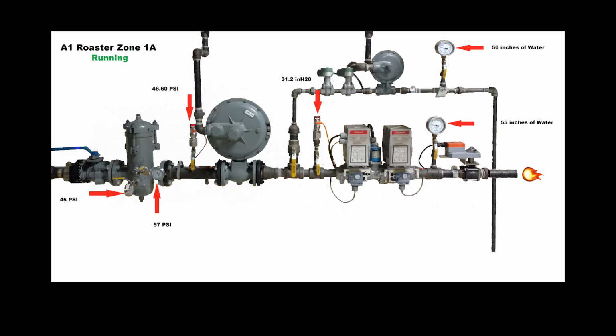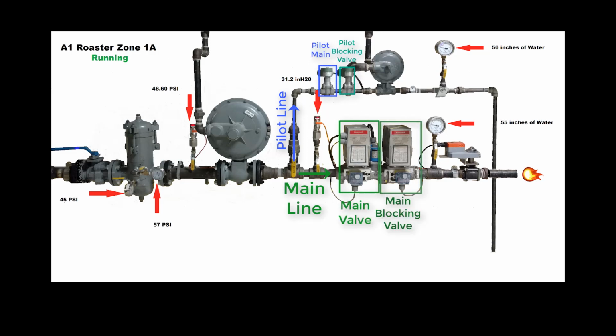Once the gas passes through the main regulator, it is then split through the main line and the pilot line. At WP&A, a double block and bleed system is in place to prevent uncontrolled gas flow in the case of valve failure. There is a main valve and a blocking valve. The double block and bleed setup is used in both the main line and the pilot line.